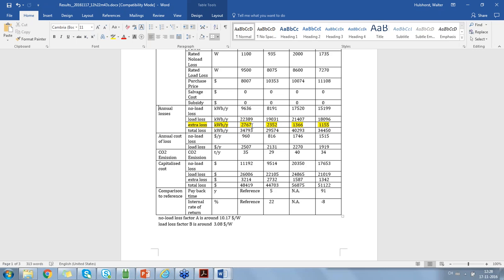So that's the reason why I already said to you, when you're ordering a transformer and you know it will be heavily loaded with harmonics, make sure that you mention it. Because if the extra losses are only calculated for cooling at, in this case, 2,700 kilowatt hours a year, and then suddenly harmonics make it pop up, it's raised to 10,000.